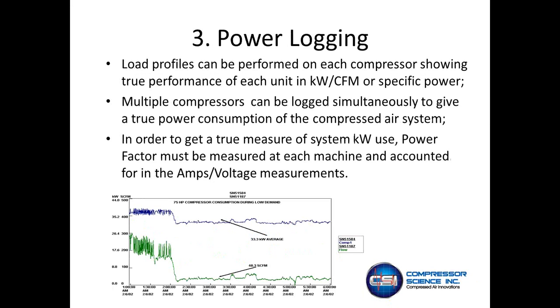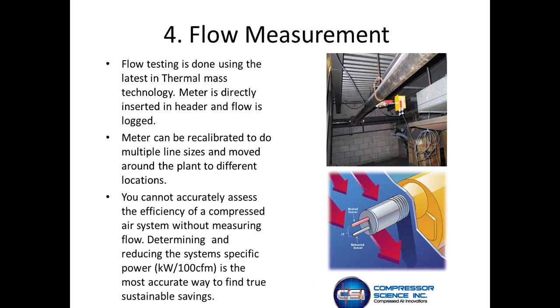Power logging and load profiles should be performed on each compressor, showing the true performance of each unit in kilowatt per CFM or kilowatt per 100 CFM, which is the specific power. Multiple compressors can be logged simultaneously to give a truer power consumption of the air system. In order to get true kilowatt consumption, you really have to look at the power factor. It has to be measured on each compressor, and you have to account for that in the amps and voltage measurements to get a true kilowatt.